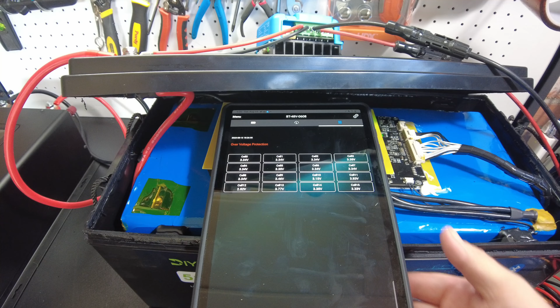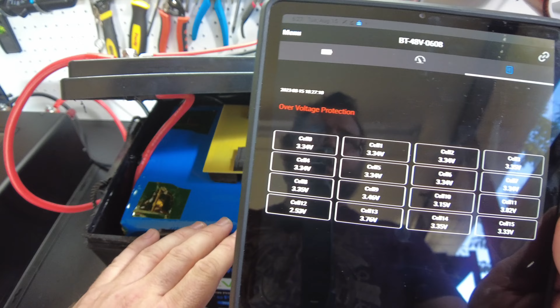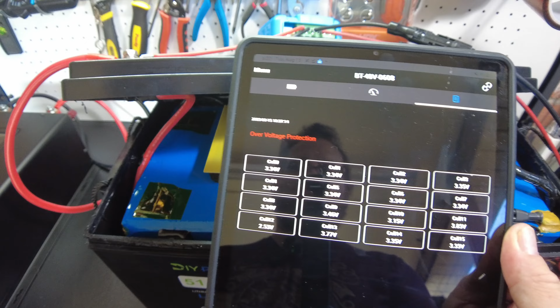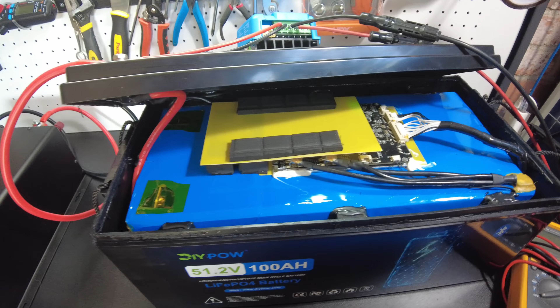All right you guys, so this thing has been sitting out here charging up for many hours, but I came out here to check on it, and it was acting strange again. I was having a hard time connecting to the BMS, but now that I'm finally connected, cell 12 is saying 2.53 volts, and cell 13 is saying 3.76 volts, and it's saying it's in over voltage protection. So the BMS is not actually allowing any charge or discharge.